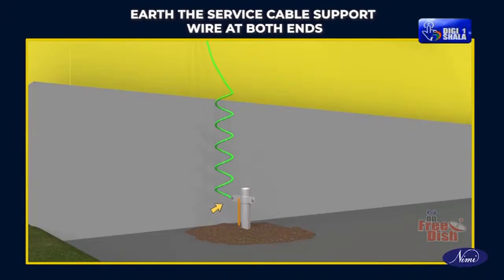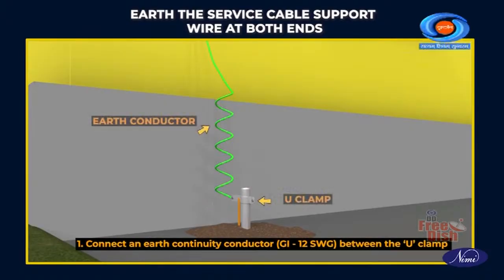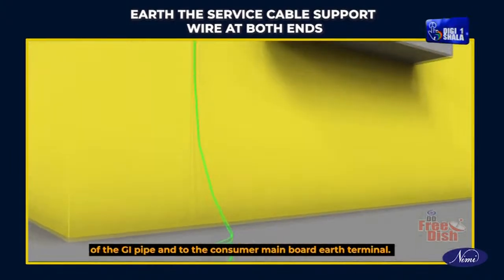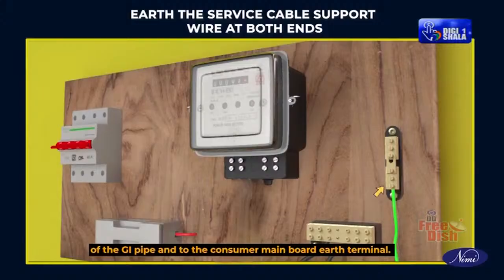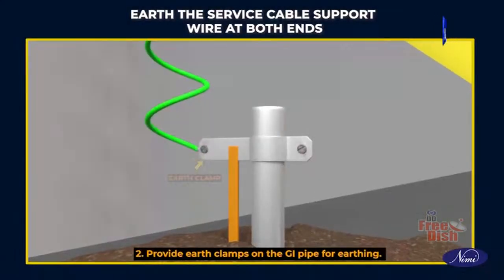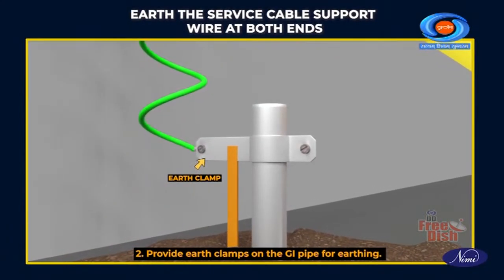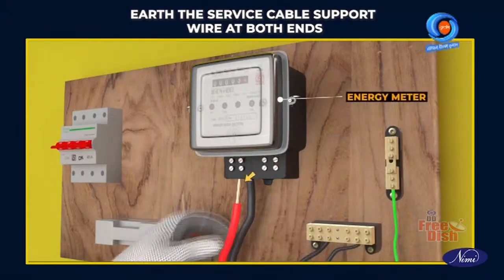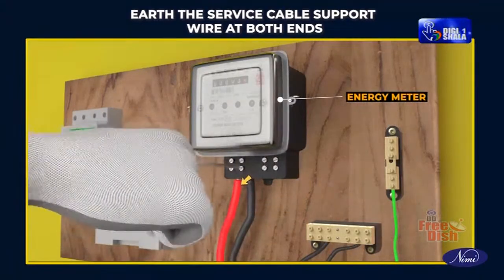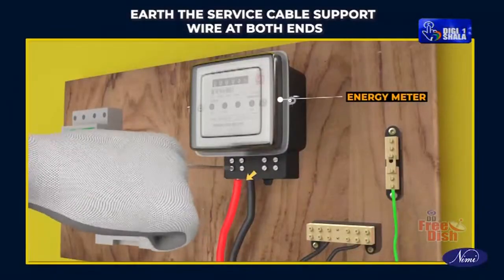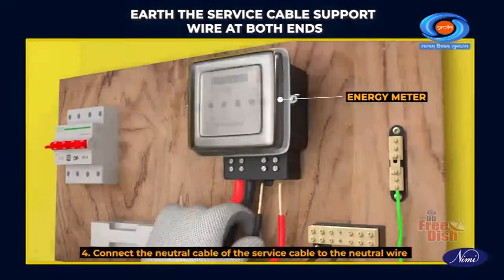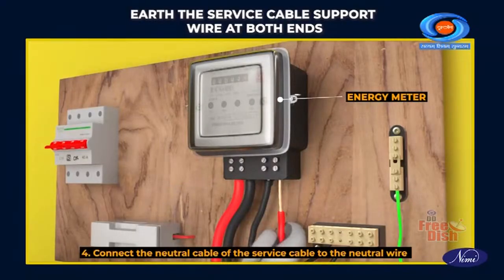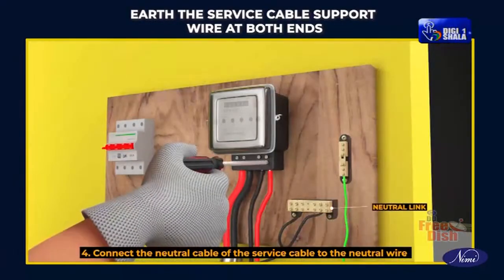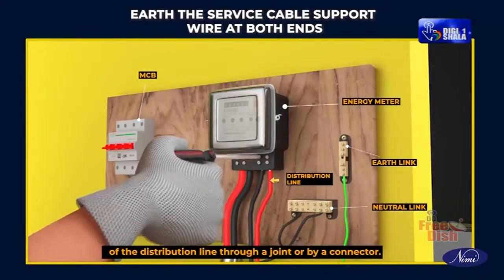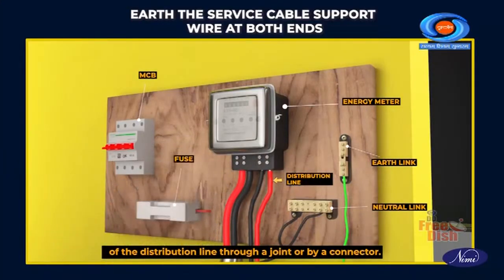Earth the service cable support wire at both ends. Connect an earth continuity conductor between the U-clamp of GI pipe and to the consumer main board earth terminal. Provide earth clamps on the GI pipe for earthing. Connect the phase cable of the service cable to the phase wire of the distribution line through a joint or by a connector. Connect the neutral cable of the service cable to the neutral wire of the distribution line through a joint or by a connector.